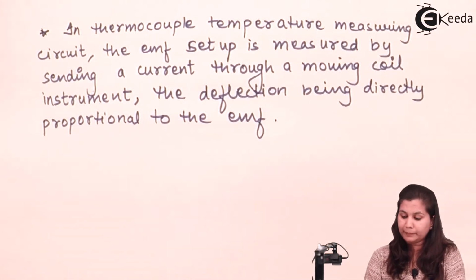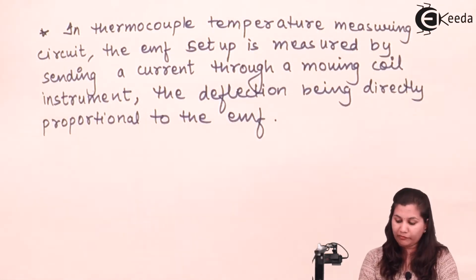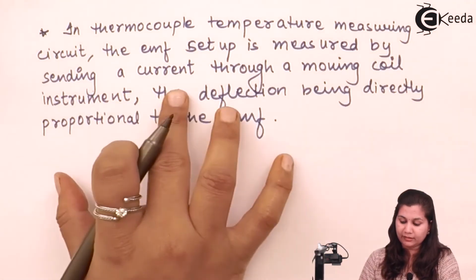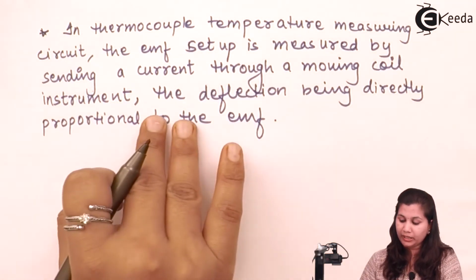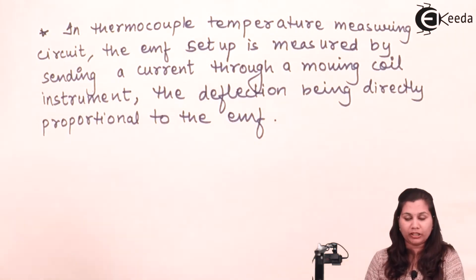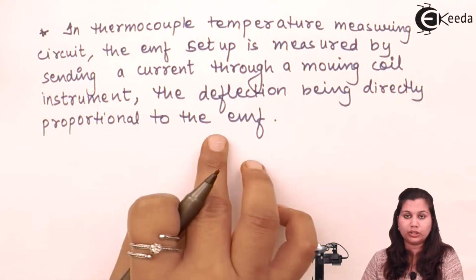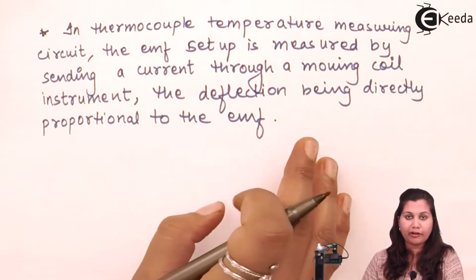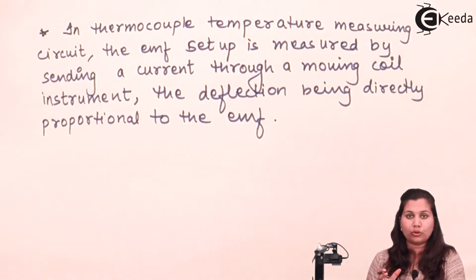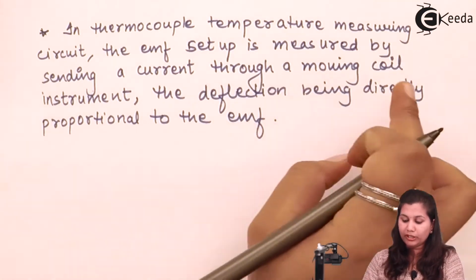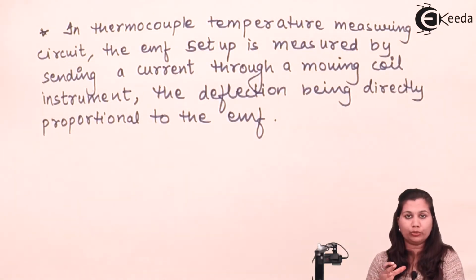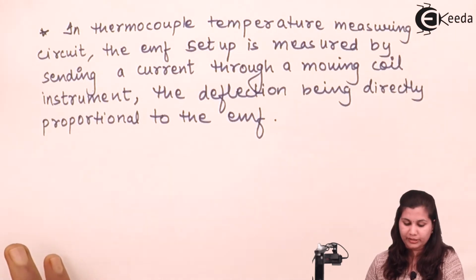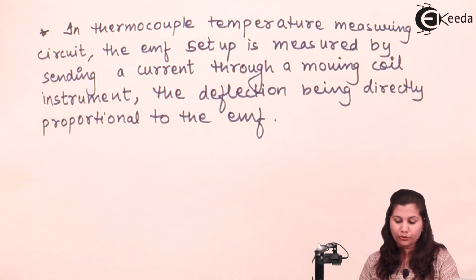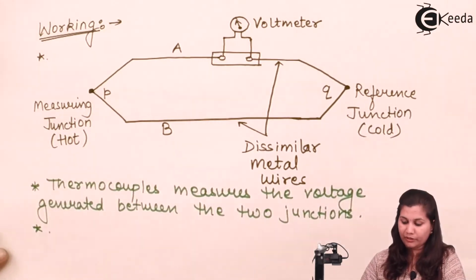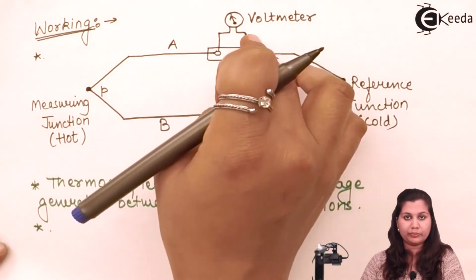So in the thermocouple temperature measuring circuit, the EMF which is set up is measured by sending a current through a moving coil instrument, and the deflection in this moving coil instrument is directly proportional to the EMF. Now EMF is a function of the temperature difference. So the moving coil instrument is directly calibrated to read the temperature difference, that is del theta. So here, if we see this diagram, we are using a moving coil instrument, or we can use a voltmeter.